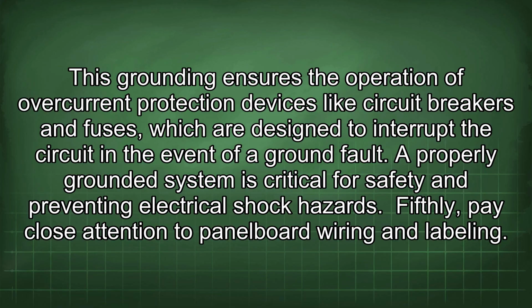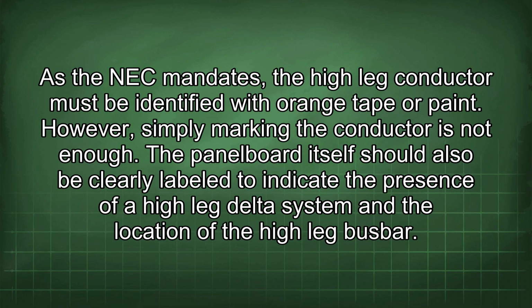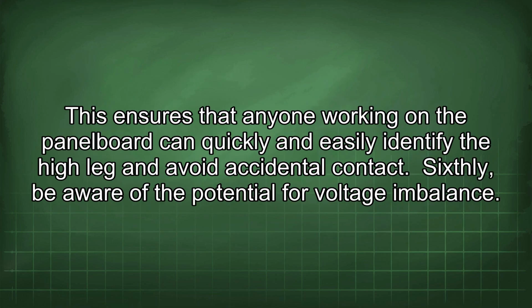Fifthly, pay close attention to panel board wiring and labeling. As the NEC mandates, the high leg conductor must be identified with orange tape or paint. However, simply marking the conductor is not enough. The panel board itself should also be clearly labeled to indicate the presence of a high leg delta system and the location of the high leg bus bar. This ensures that anyone working on the panel board can quickly and easily identify the high leg and avoid accidental contact.